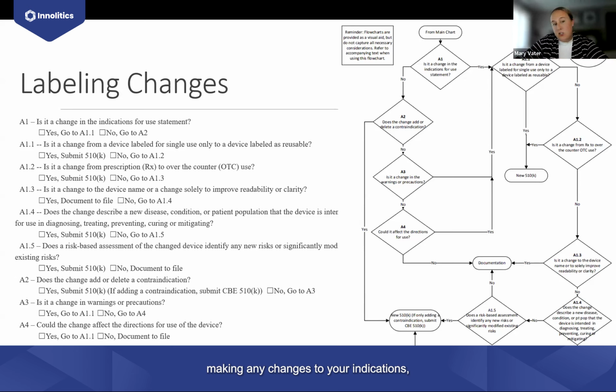If you're making any changes to your indications that's just intended to clarify how it's used, or to stay within the same intent but modifying it for clarity, then there's some flexibility there. But of course, if you're adding new functions or new features, or expanding your indications, or making them more specific indications, like for a specific disease or something, lots of those things would trigger a new 510K. So certainly an important one that oftentimes would trigger a new 510K.